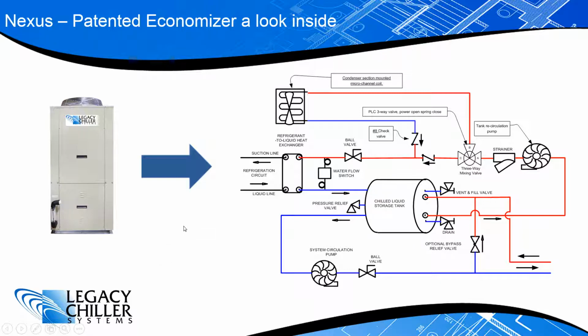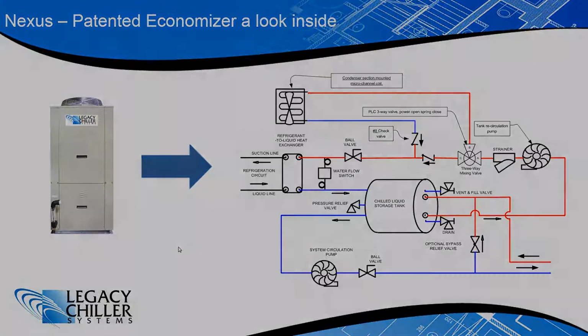This system is very, very effective, as I mentioned earlier, if you have a high set point process and you tend to have cold outdoor ambient. So this is a very, very cost-efficient way, in some cases up to 60% savings if you have the right application in the right climate. All right, that is the economizer operation. I hope that information is helpful to you.